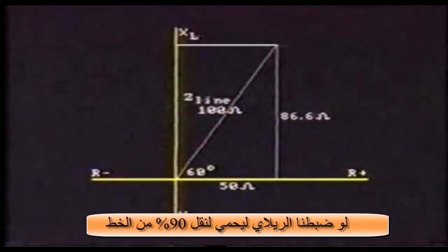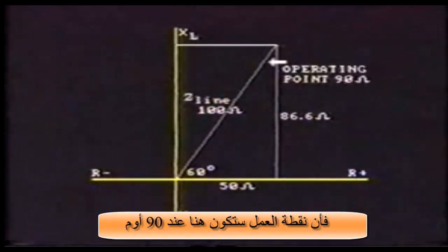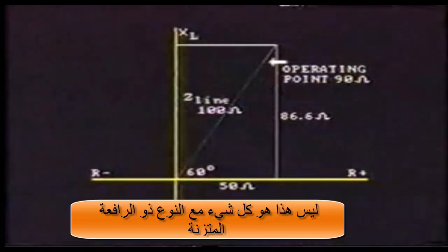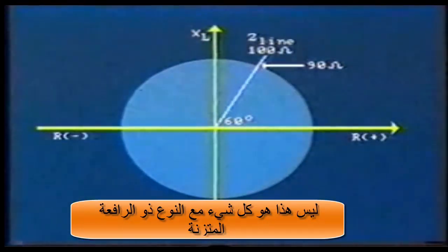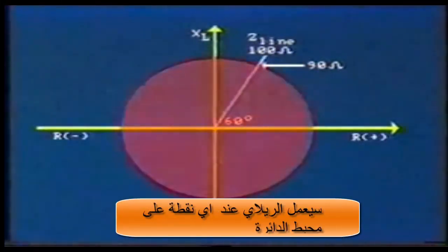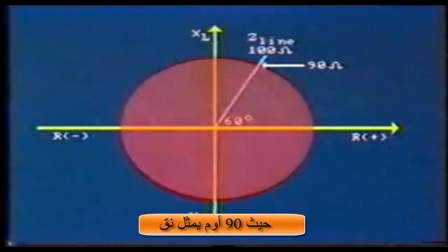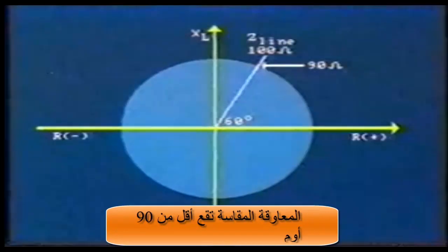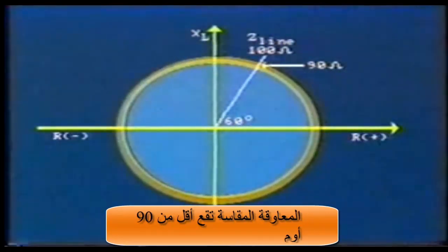If we were to set our relay to protect 90% of this line, then the operating point would be here at 90 ohms. The relay would operate for any impedance along this line between 0 and 90. With the simple balanced beam type relay, it would operate for anywhere within this circle, where 90 ohms is the radius. The balanced beam does not take into account phase angle or direction of current flow — it will trip as long as the measured impedance falls below 90 ohms.